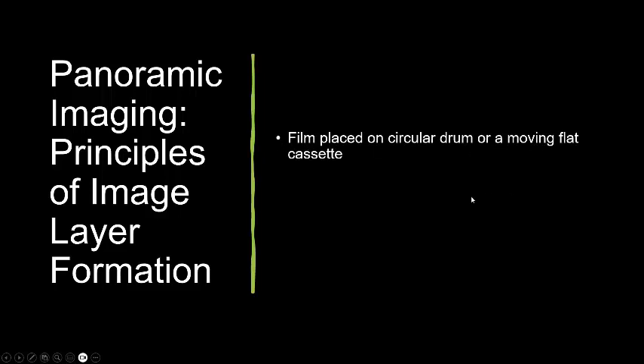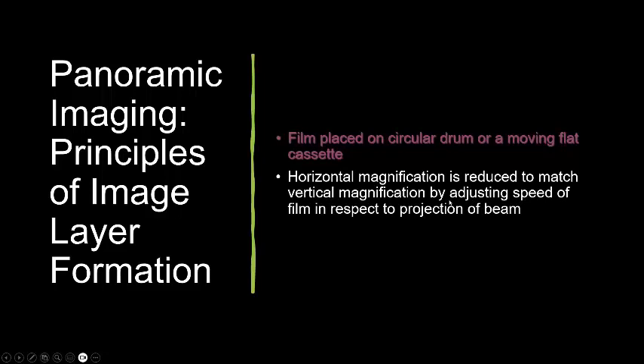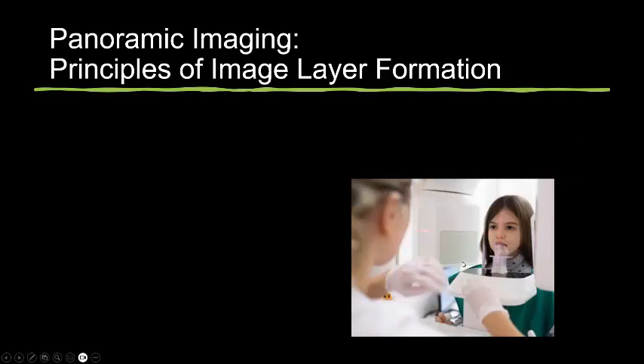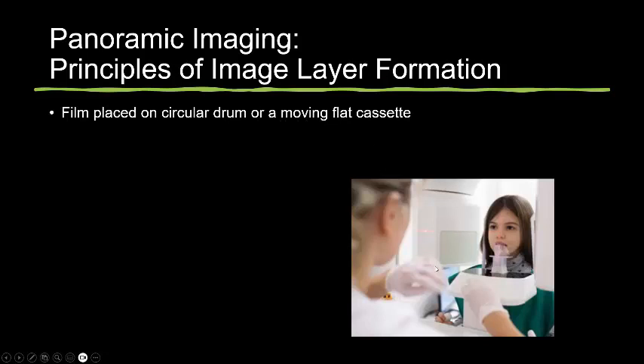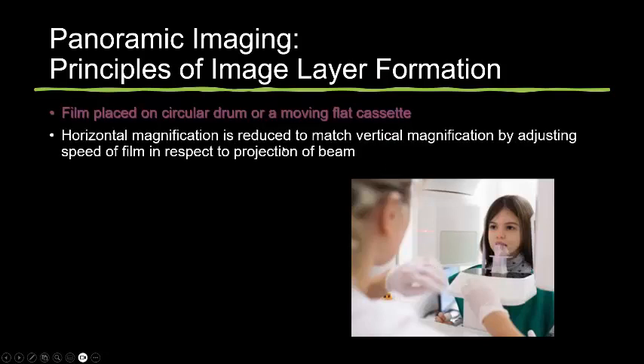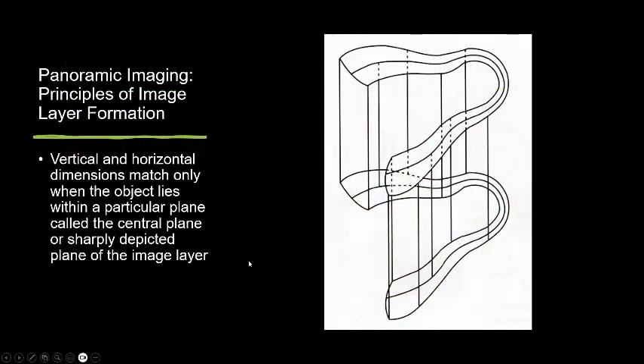For layer formation, the film is placed on a circular drum or a moving flat cassette. Horizontal magnification is reduced to match vertical magnification by adjusting the speed of the film relative to the projection of the beam. Vertical and horizontal dimensions match only when the object lies within a particular plane — the central plane or sharply depicted plane of the image layer, known as the focal trough.